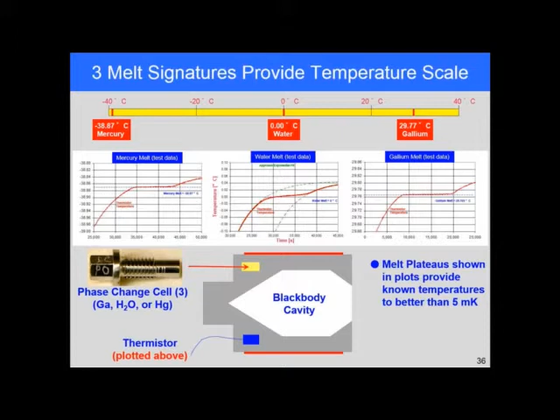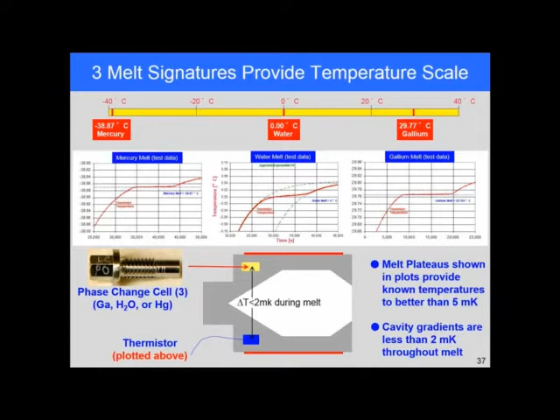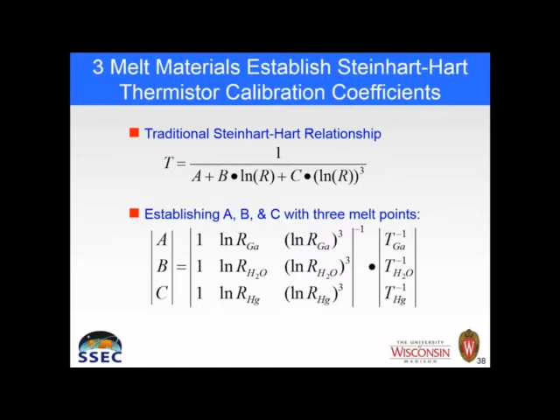And because the process is done slowly, there are very low gradients in the system, something on the order of 2 millikelvin. So we know that what happens here can be tracked here within this 2 millikelvin uncertainty. And because we have 3 temperatures, when we go through each melt, we measure the resistance of each thermistor at that temperature. So then we have 3 equations and 3 unknowns to fill in a traditional relationship for thermistor temperature sensors. It's called the Steinhart-Hart relationship. And so we can develop calibration coefficients for each of those sensors by going through the 3 different melts.